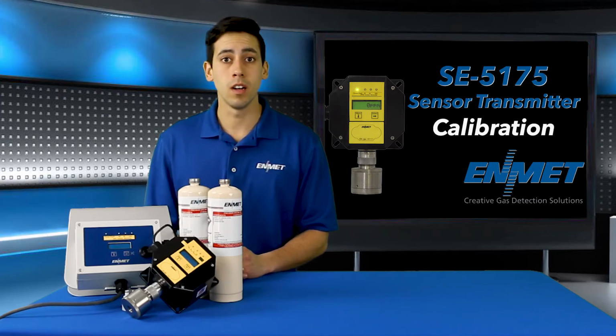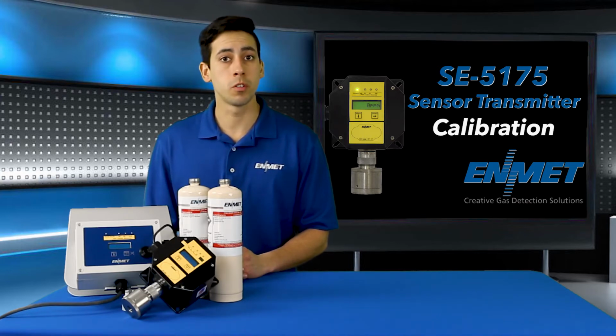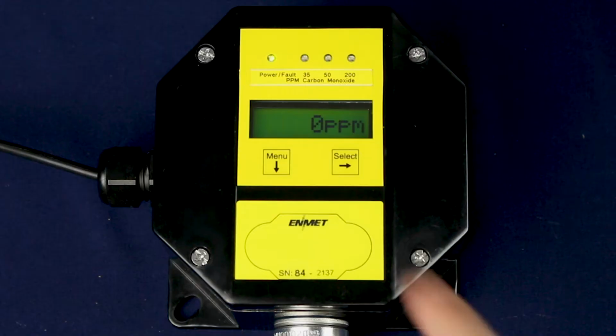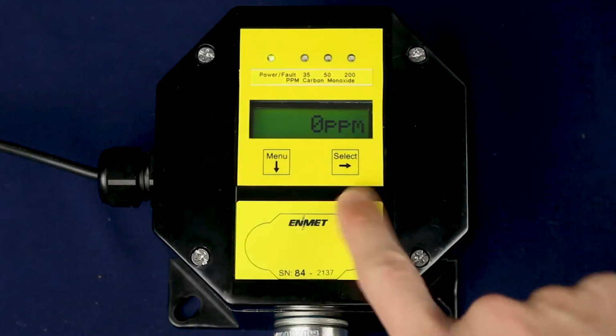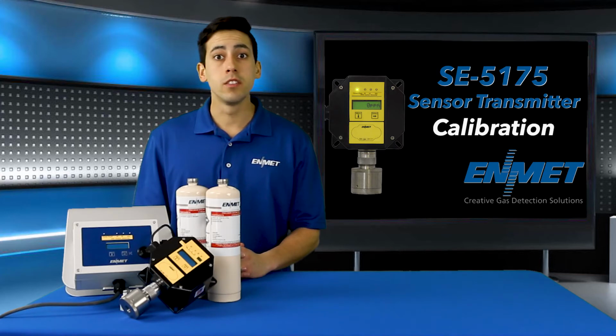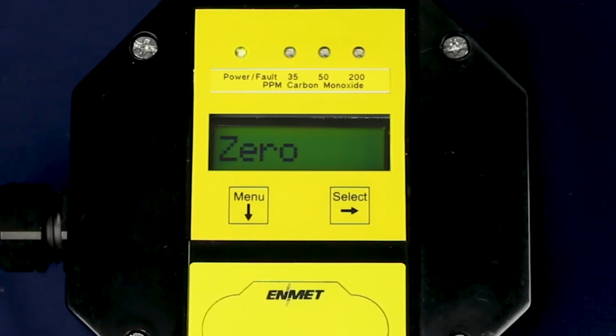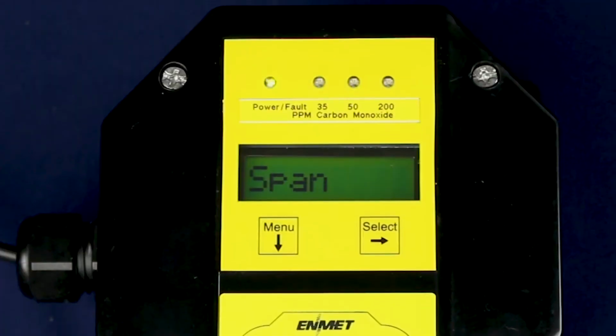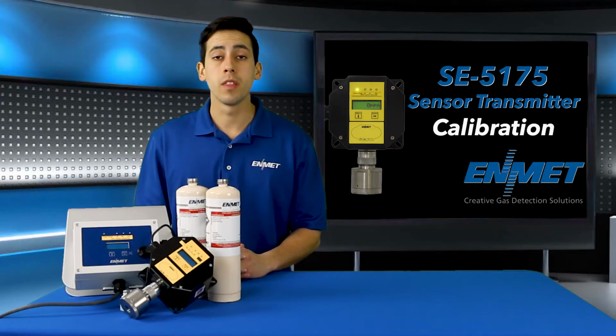It is not necessary to open the enclosure to make an adjustment. The calibration functions are operated with the push buttons from outside the enclosure through the menu and the select switches. The calibration zero and span functions are two separate procedures that operate independently of each other. It is recommended that the zero procedure be done prior to the span procedure. Please note that the zero function is not used for oxygen transmitters.